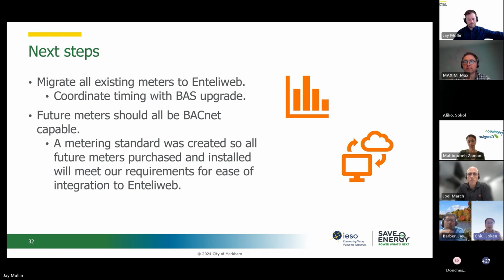In addition, any meters we purchase in the future, we're going to ensure they're BACnet ready, which makes it easy to integrate to Enteliweb. Some of the meters we had in the past only communicated using Modbus, so integrating to Enteliweb wasn't difficult, but there's an extra step adding a gateway to translate Modbus to BACnet so it can communicate with the BAS system. Because of that, we designed a metering standard to make sure any meters we purchase from now on integrate easily and fulfill our metering requirements as well.